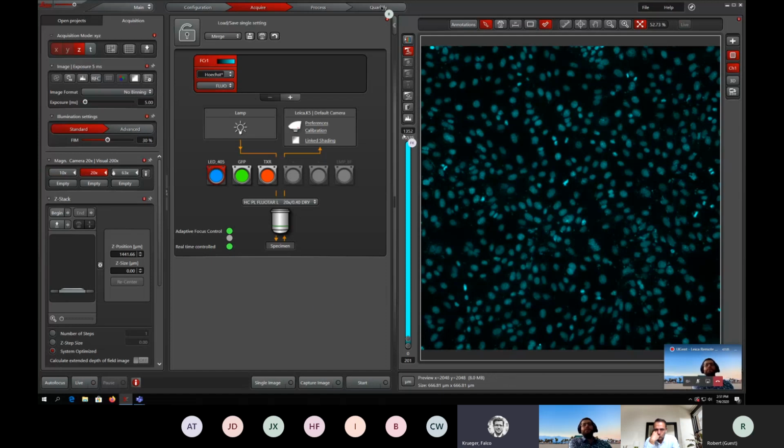Again, here we check. The brightest pixel is 1300. The darkest is 200, so it's roughly 6:1 as a signal to background ratio, which is also super nice for the Thunder and computational clearing methods. Maybe here a rule of thumb would be between 4:1 and 10:1. The quality of the processing is best. Everything above 10:1 actually doesn't change anything anymore in your image, and everything below 4:1 can be critical in terms of image quality that you will get. This is something to note, maybe.